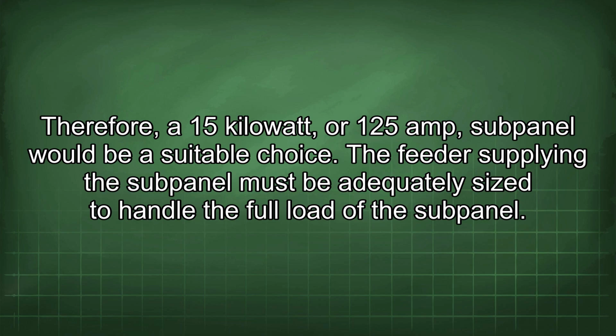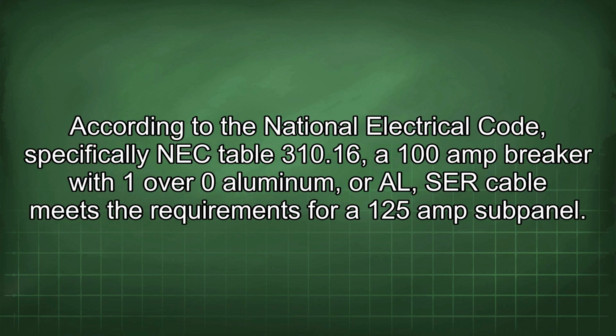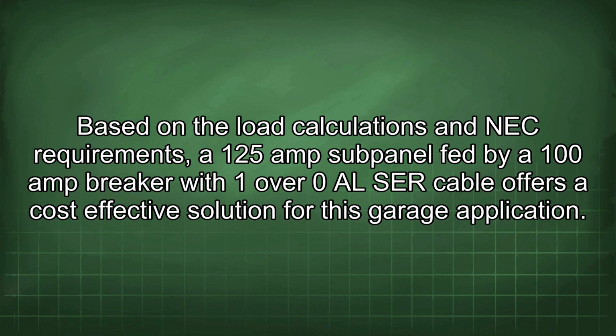The feeder supplying the subpanel must be adequately sized to handle the full load of the subpanel. According to the National Electrical Code, specifically NEC Table 310.16, a 100 amp breaker with 1/0 aluminum or AL SER cable meets the requirements for a 125 amp subpanel. Based on the load calculations and NEC requirements, a 125 amp subpanel fed by a 100 amp breaker with 1/0 AL SER cable offers a cost-effective solution for this garage application.